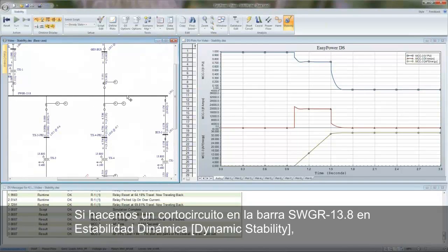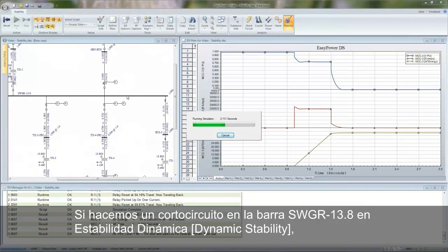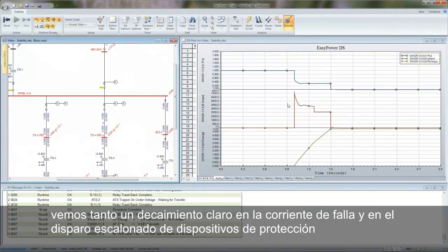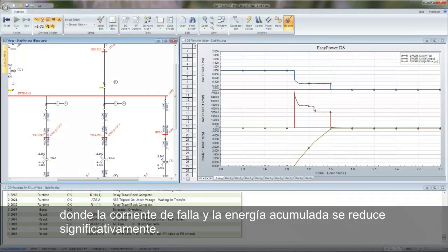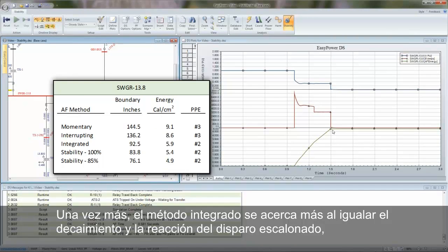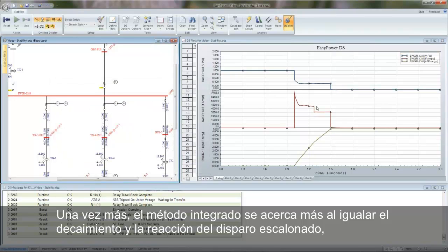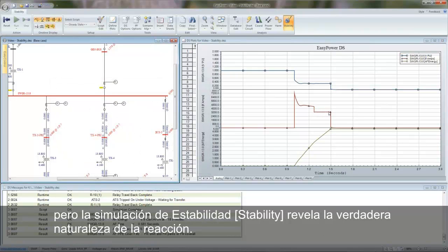If we fault bus switchgear 13.8 in dynamic stability, we see both a clear decay in fault current and protective device staggered tripping, where the fault current and accumulated energy drops significantly. Again, the integrated method comes closest to matching the decay and staggered tripping response. But the stability simulation reveals the true nature of the response.